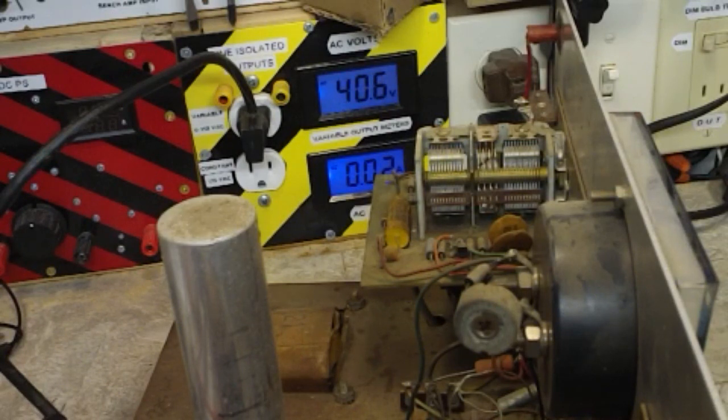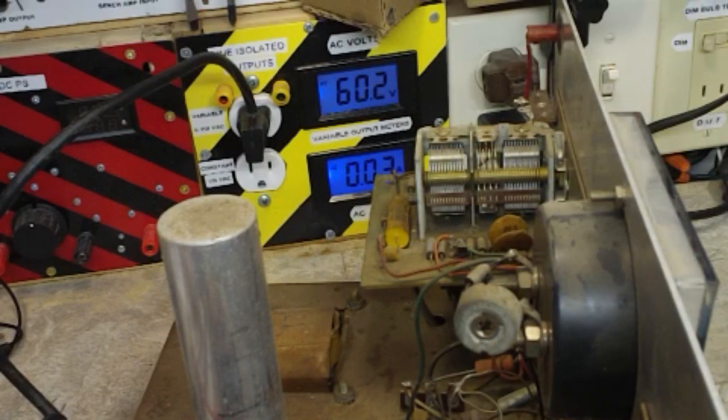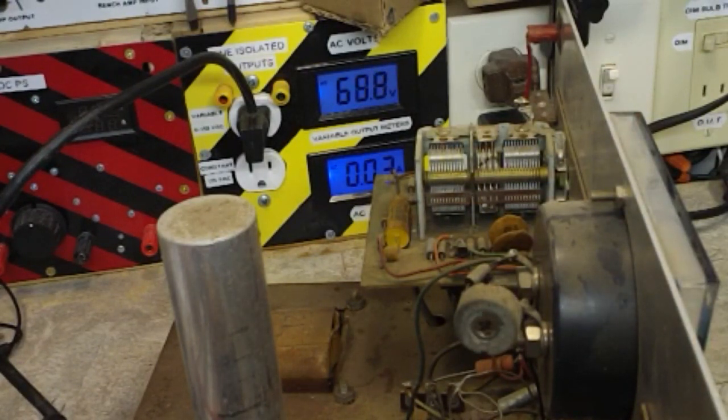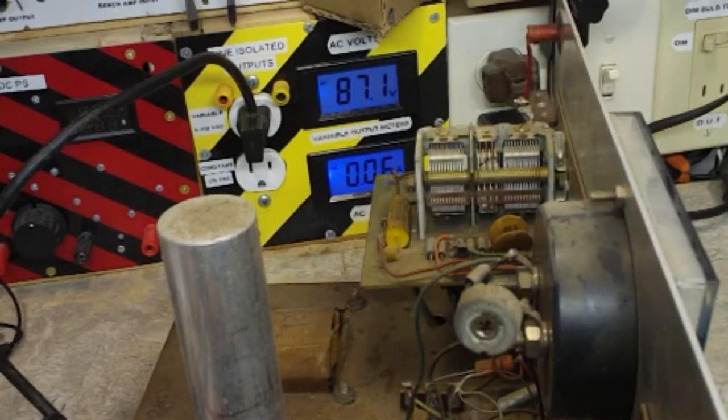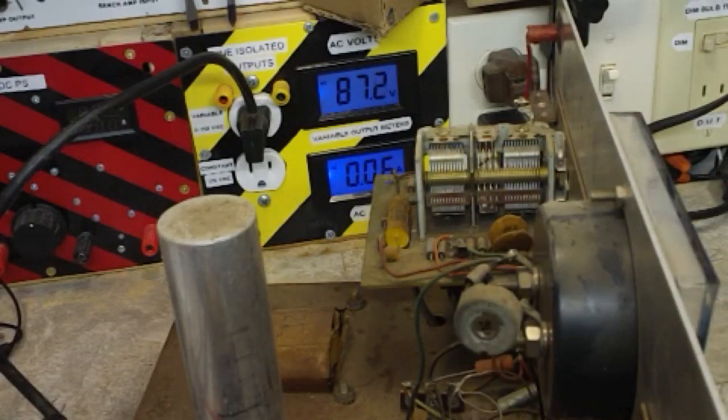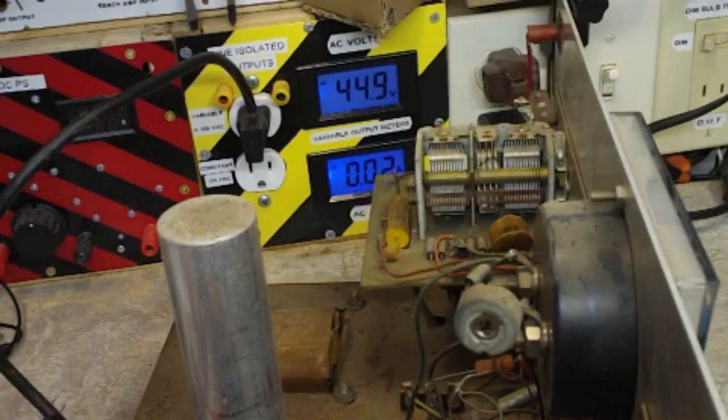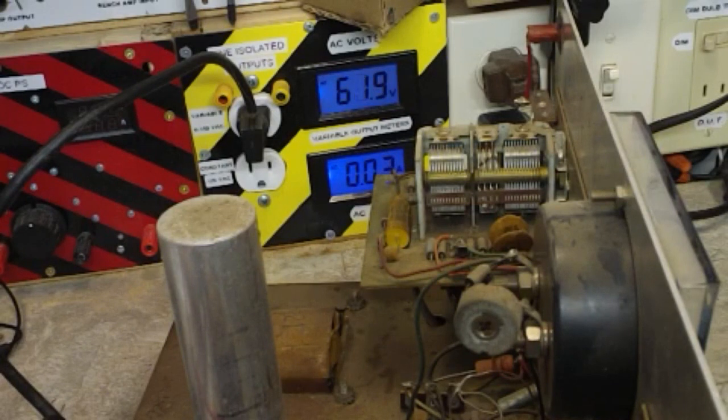Alright, we are back. I have the leads connected here on the bridge rectifier. The red one goes to the positive, the black one is going to the negative. The only thing in circuit really, other than the transformer, is this here. And we are measuring 0.49 volts with the unit off and the Variac turned all the way down. I'm going to say that capacitor is storing a charge. Alright, what we're going to do is turn the unit on and take some voltage up. See if we get any kind of action. Alright, I'm up to 40 volts. I have 0.543. So it is actually going up.